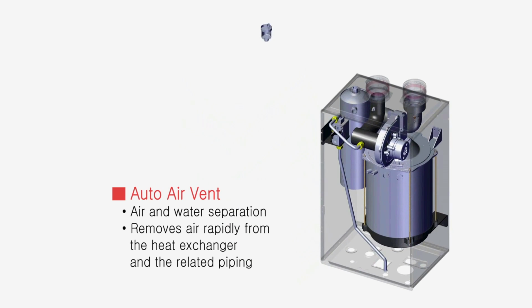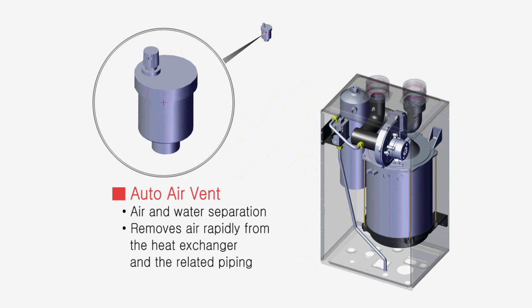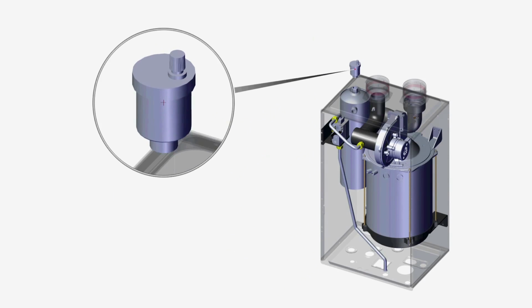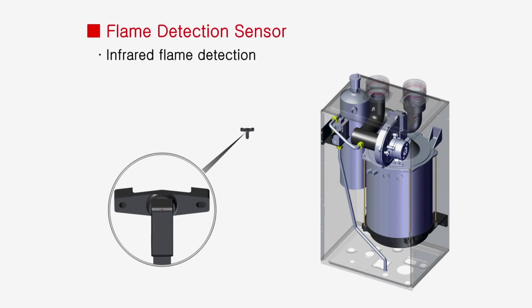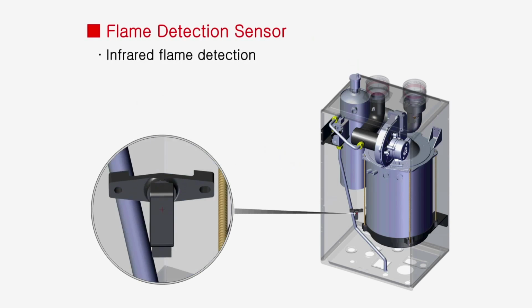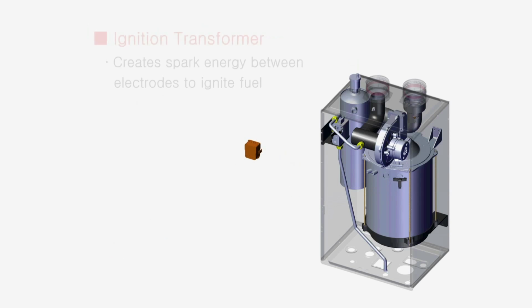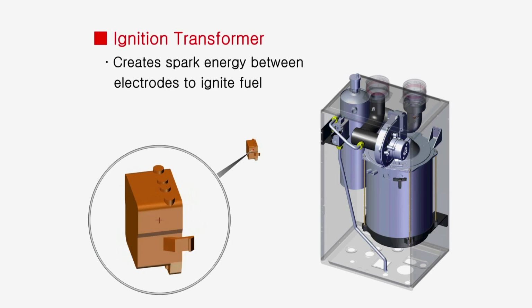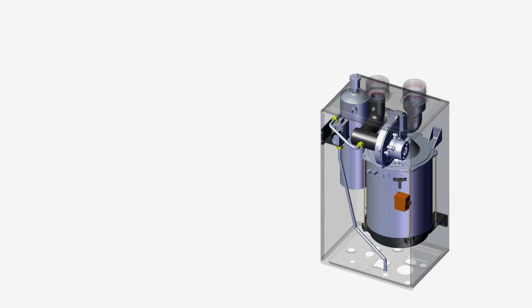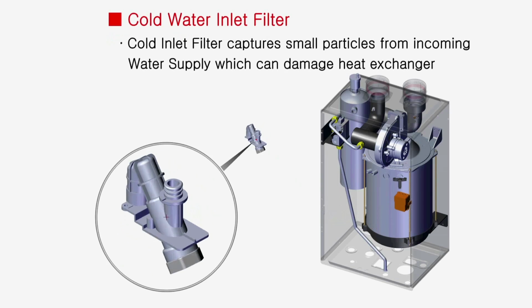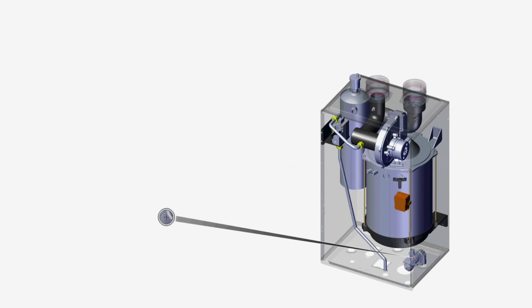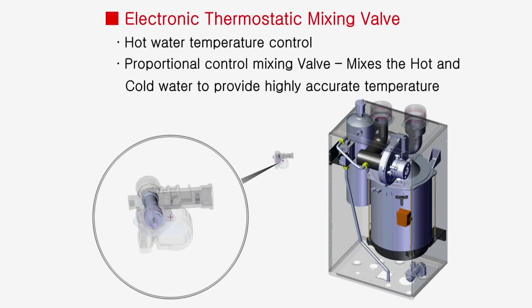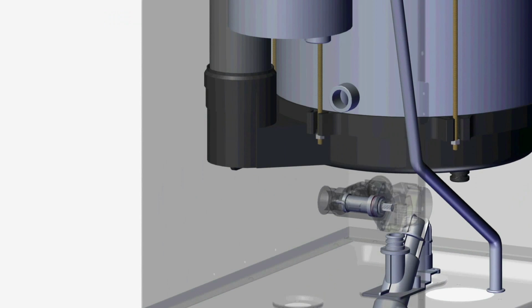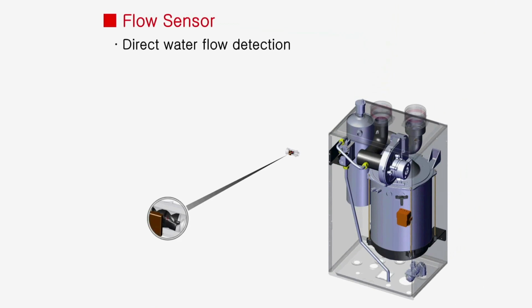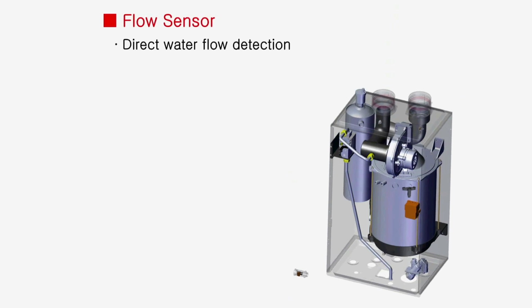Auto air vent allows the air inside the pipes to be automatically discharged. A flame detector senses the flame when infrared radiation emitted by flame goes over a setting amount. An electric transformer discharges continuously high voltage by electric energy in order to supply ignition energy to the burner for ignition. Cold inlet filter captures small particles from incoming water supply, which can damage the heat exchanger. The mixing valve mixes the hot and cold water to provide highly accurate temperature control. The flow sensor serves to monitor the domestic water flow and fire the boiler combustion system to meet the hot water demand.